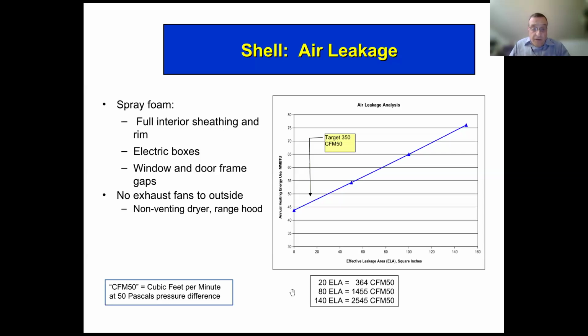So for people not familiar with blower door testing, North American standard is to create a pressure difference between inside and outside of 50 pascals. That's the standard. And then you measure the airflow, which would equate to the amount of leakage in the house. And that's what the ELA is, an effective leakage area in square inches. So 350 CFM 50 would equate to just something under 20 square inches of effective leakage area.